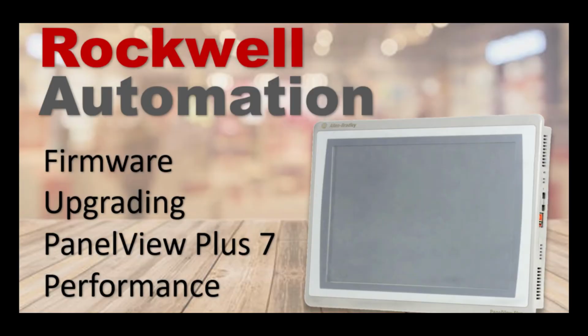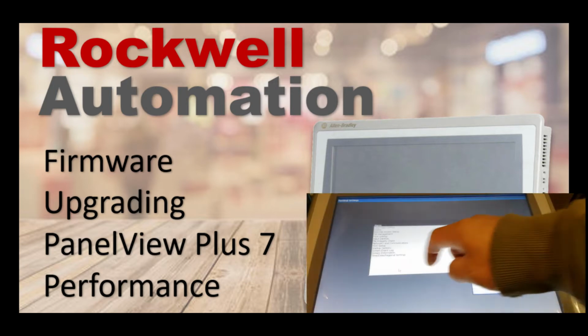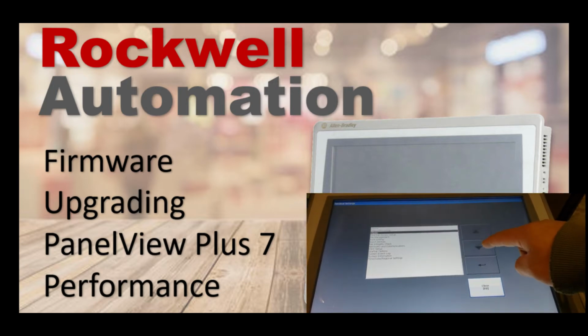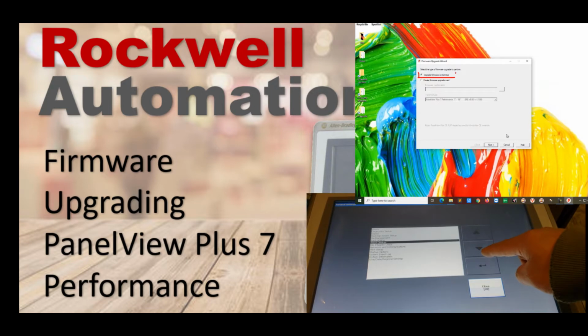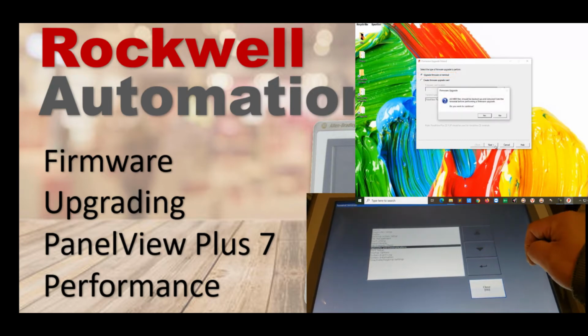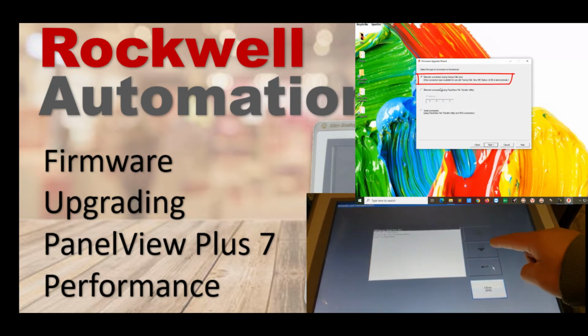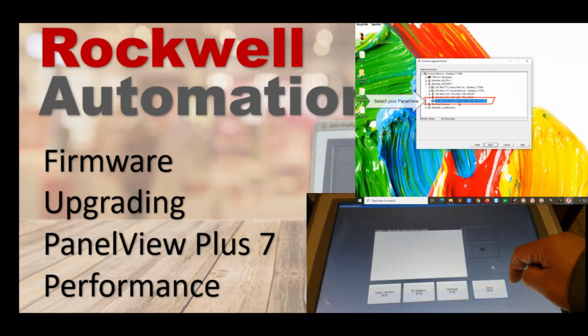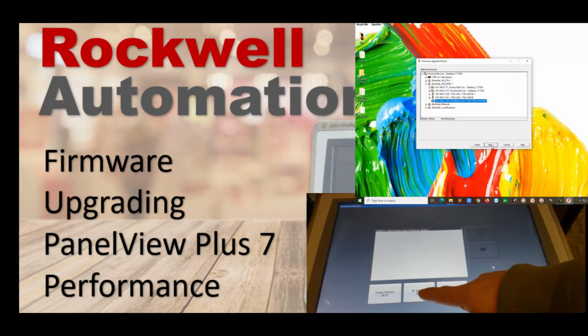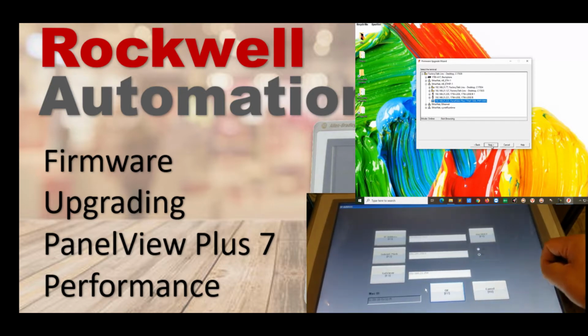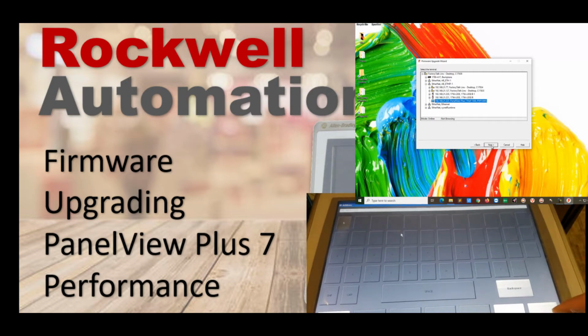In this episode, I'll demonstrate how you can apply a firmware version on your Allen Bradley PanelView Plus 7 Performance. Essentially, there are two steps to getting it done. First of all, set up your IP address on your PanelView. And the second step is to install the ME Firmware Wizard loader. Let's get started. Well, the first step is to set up the IP address.